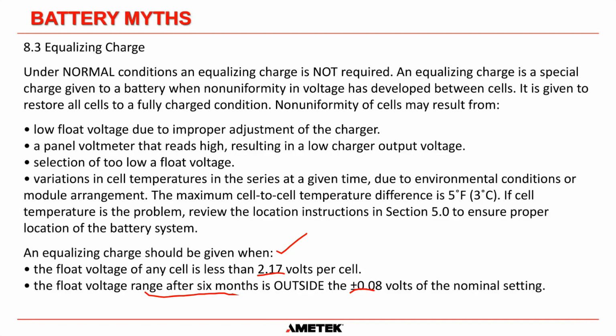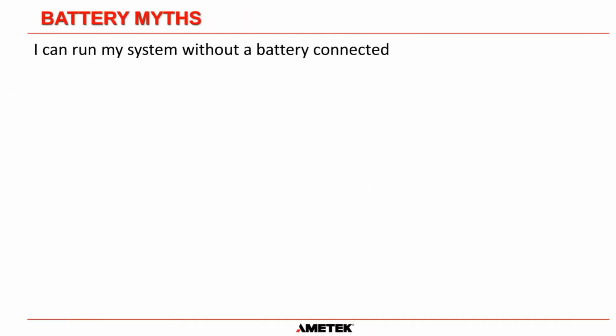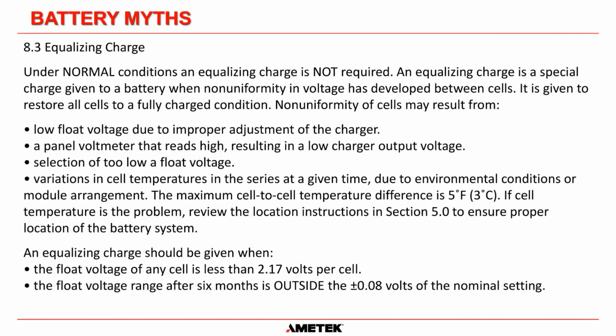So let me explain that. Let's say the recommended float voltage is 2.25 volts per cell. What they're saying here is if the cell voltage goes to 2.17 or to 2.35, sorry, 2.33, is it? 2.25 plus 0.08. If it goes outside that band, then you can do an equalize. And then it tells you what that equalizing charge should be.